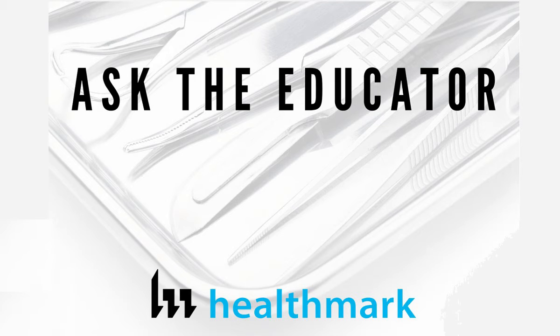You also should not be using multiple detergents. As I was mentioning recently, we've seen it more than a few times at sites where the pre-cleaning sponge that already has detergent follows the scope into the processing area. They continue to use that same sponge that has detergent in it, and then they're adding different detergent into the wash water. So you potentially have chemical interference, with highly concentrated detergent.